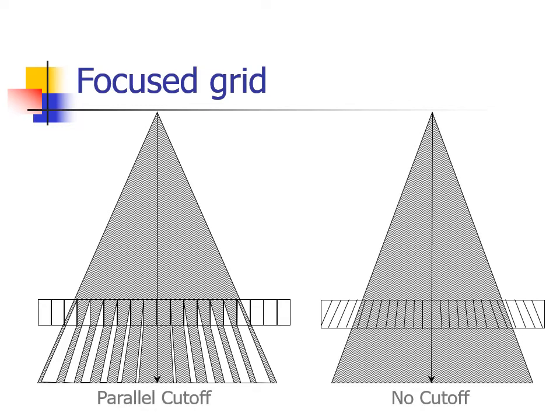With the parallel grid, when radiation is projected through it, the grid cuts off the peripheral rays. With the focused grid, the angle of the lead strips mimics the angle of the X-ray beam, thereby eliminating cutoff.